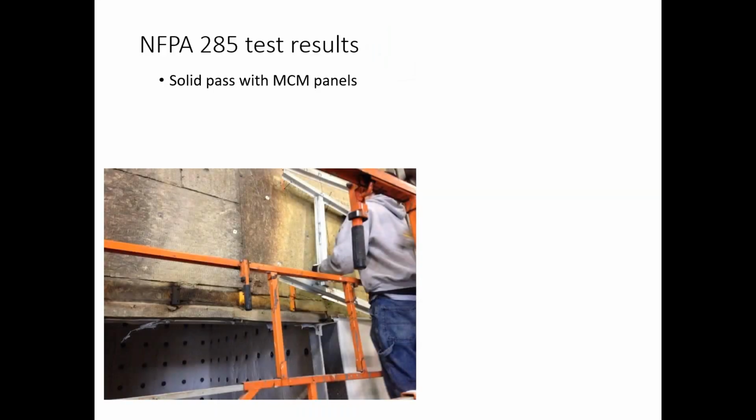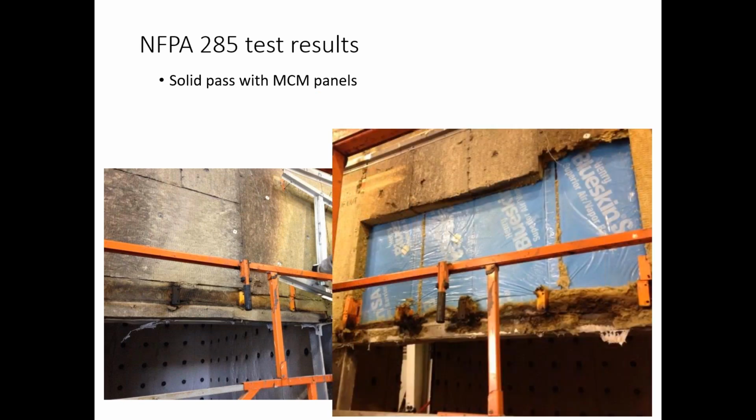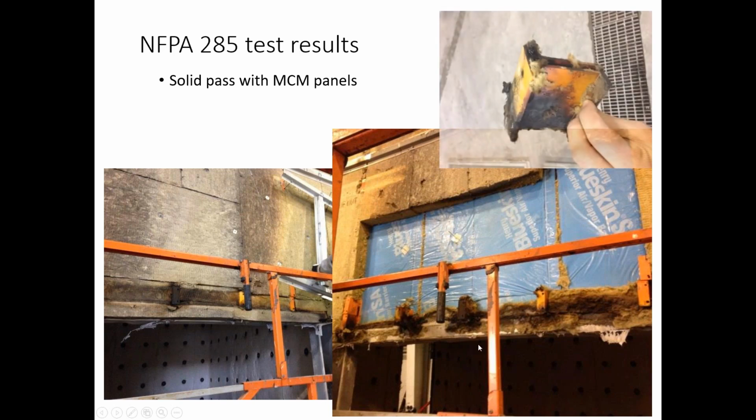So we have this pass at the end of this test, and then we take it apart and we examine the parts. And the parts, the combustible parts, like the thermal spacer, that were right at that window opening, getting the full brunt of the fire for half an hour, were definitely charred because they're combustible materials, but they were still structurally intact. I stood on that. That's actually my hand holding that part. I took it, I stood on it, I shipped it back to our shop. It's still in one piece today.